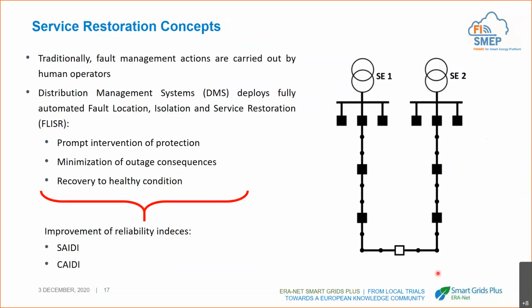2 feeders that are managed in medium voltage. These are related to 2 different substations. This is one feeder and this is the other. And the black square is the closed circuit breaker, and the white square is the normally open circuit breaker, which means that these 2 feeders are electrically disconnected. Each point that we have here is a load that we have in the electrical grid.